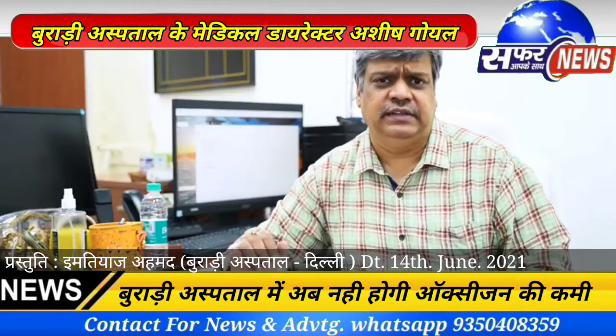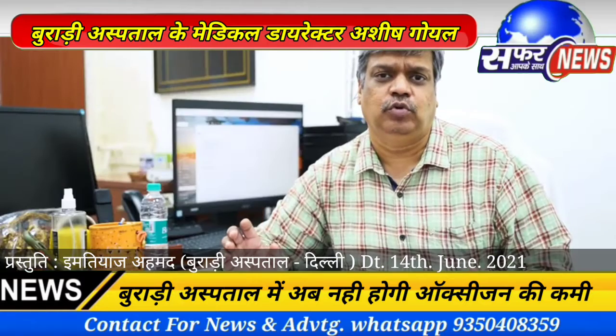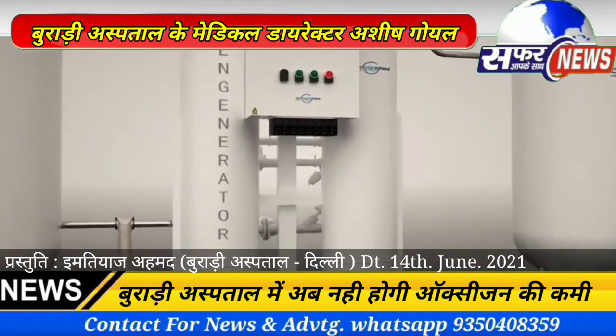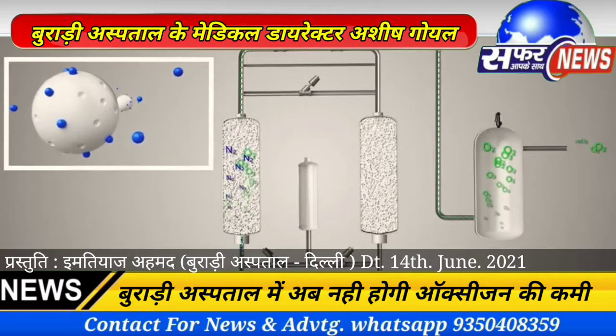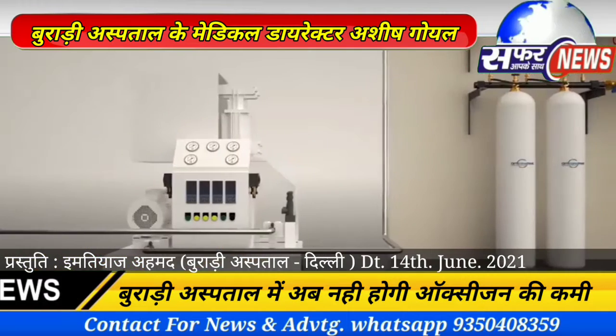We give continuous oxygen. How do these plants work? The atmosphere contains about 21% oxygen. We take air from the atmosphere and remove nitrogen from it, so the resulting oxygen concentration is 95% or higher — and that is what is supplied to the patients.